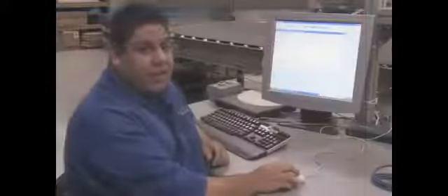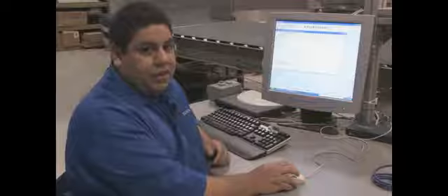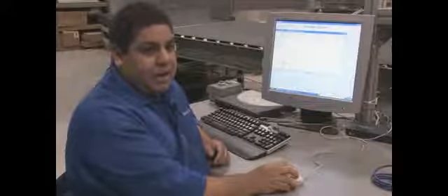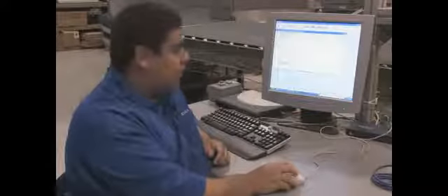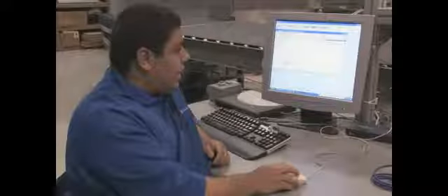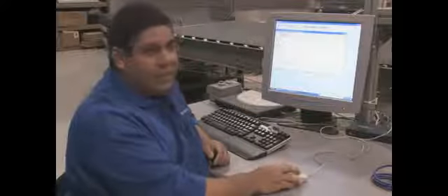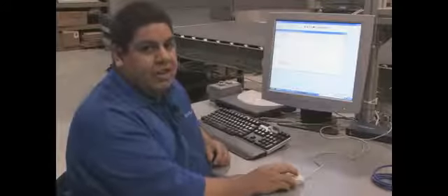By default, there will also be data flow control enabled. This is called the DAD driver. This DAD driver is used for data resynchronization, data fragmentation, flow control, and things of that nature. But for right now, we're going to disable it, that way we can see the data in our PLC. You can read more about that DAD driver in the manual that's on the Genius CD.